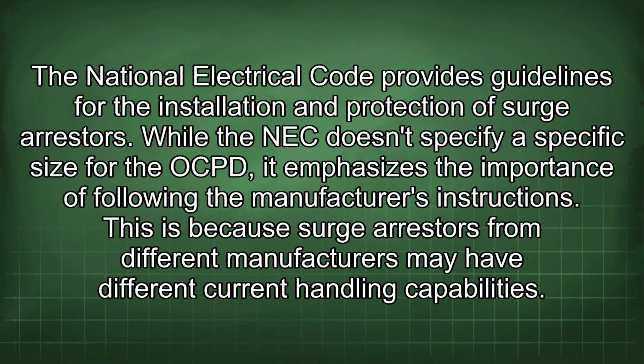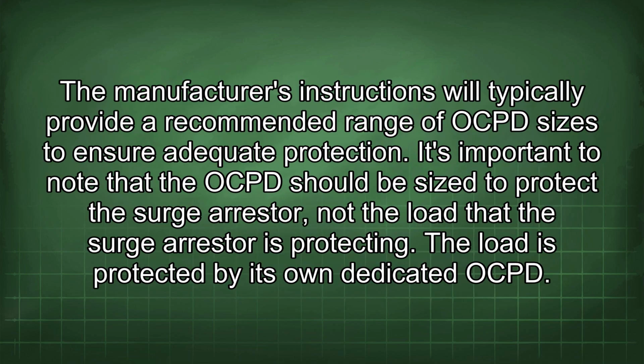The National Electrical Code provides guidelines for the installation and protection of surge arrestors. While the NEC doesn't specify a specific size for the OCPD, it emphasizes the importance of following the manufacturer's instructions. This is because surge arrestors from different manufacturers may have different current handling capabilities. The manufacturer's instructions will typically provide a recommended range of OCPD sizes to ensure adequate protection.